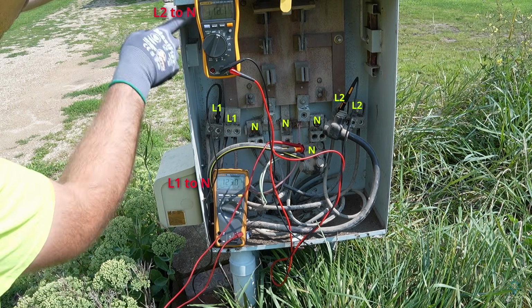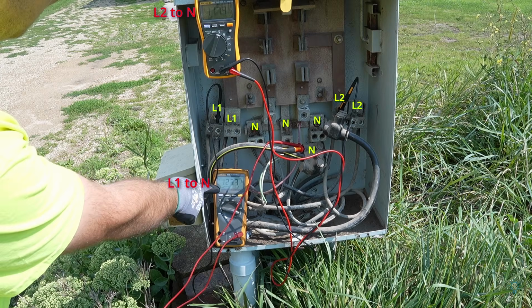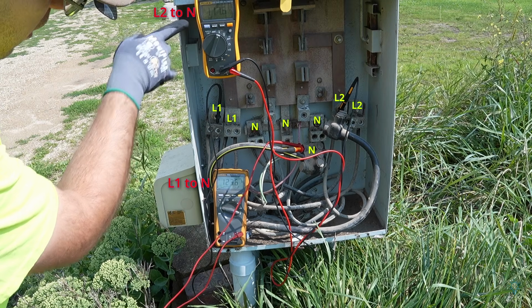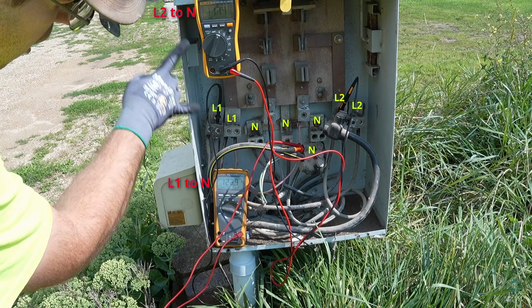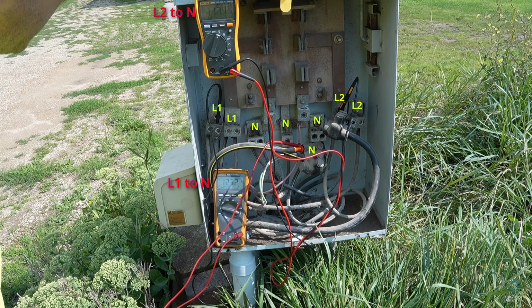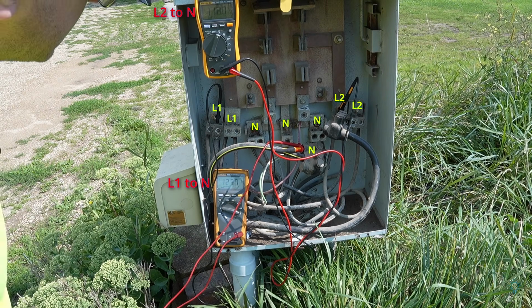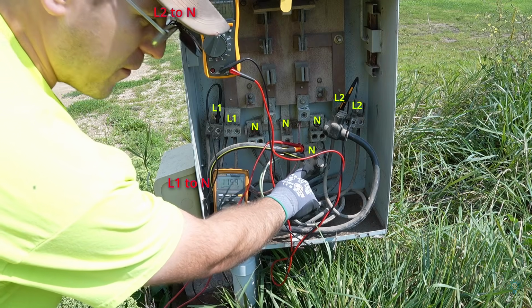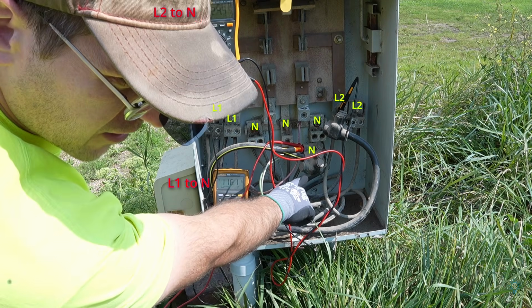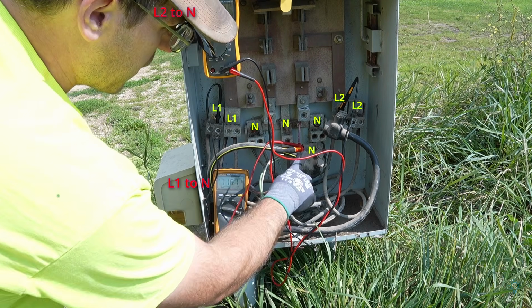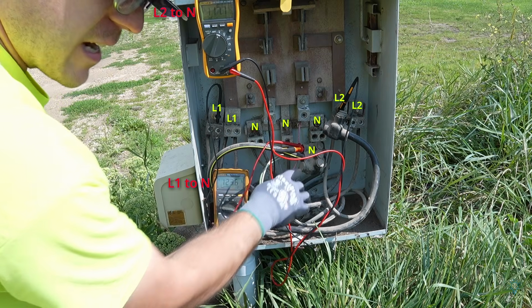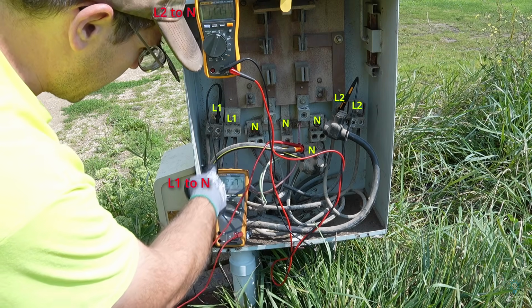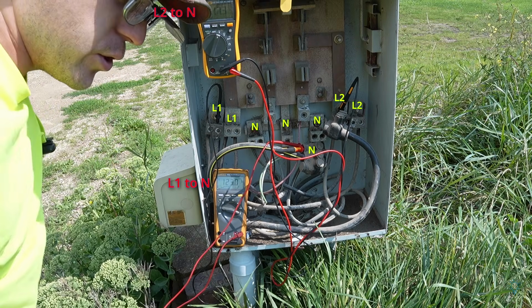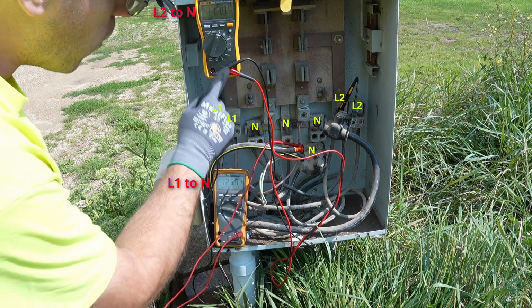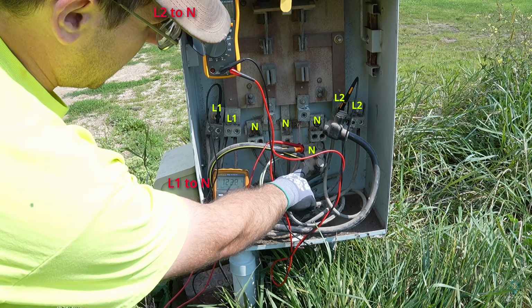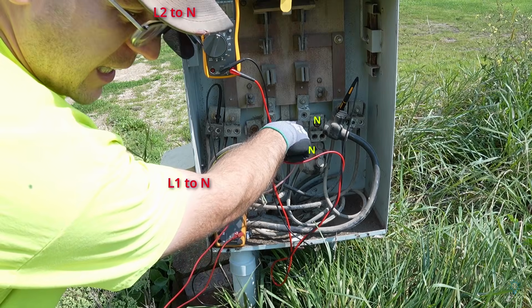And there the voltage is swapped again now. So this one's higher now and this one's the lower. I mean, they're pretty darn close. I would call that fairly well balanced. That's within tolerance. This is measuring it right off of this neutral Polaris connector right here. So this is measuring to this Polaris connector. Now what that tells me is that this neutral running underground to the house is okay. We are losing that somewhere between here and that lug in the back.